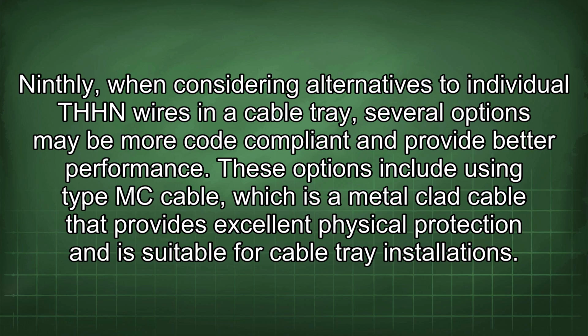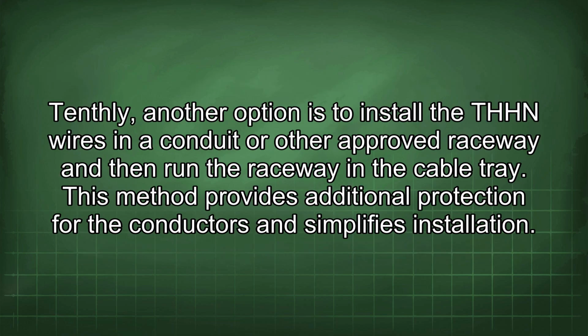Ninthly, when considering alternatives to individual THHN wires in a cable tray, several options may be more code compliant and provide better performance. These options include using Type MC cable, which is a metal-clad cable that provides excellent physical protection and is suitable for cable tray installations. Tenthly, another option is to install the THHN wires in a conduit or other approved raceway and then run the raceway in the cable tray. This method provides additional protection for the conductors and simplifies installation.